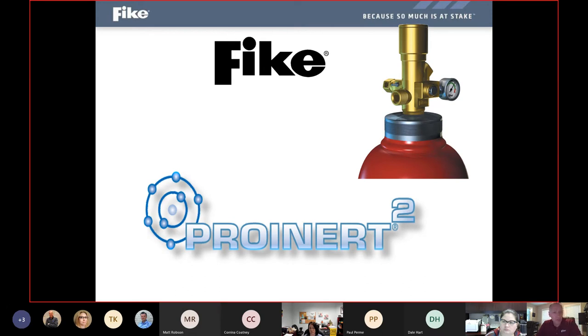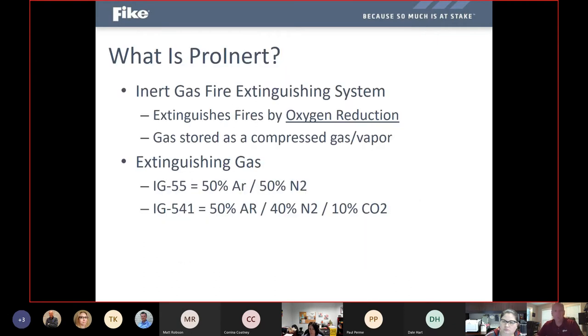Another option from a clean agent standpoint is inert gas systems. So the Fike Pro Inert system is an inert gas fire extinguishing system, and where the chemical agents reduce or extinguish a fire by a chemical reaction and heat absorption, inert gas systems extinguish by oxygen reduction. So again, it's not oxygen displacement like with CO2. Carbon dioxide systems are complete oxygen displacement. So you do not want to be in an area or a room that has a CO2 system because you will not be able to breathe.